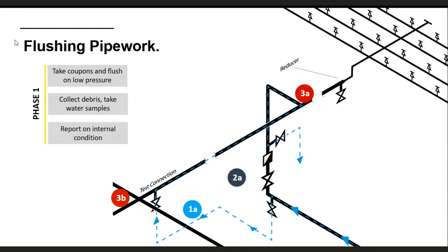The water supply, and then you divert it around the alarm valve and put it into the test connection at the remote point, and you push the water back and then take it out from above the alarm valve. So you're kind of flushing in reverse. The idea is that the pipework gets smaller as it goes from the alarm valve to the sprinkler heads. That's just the way it is.